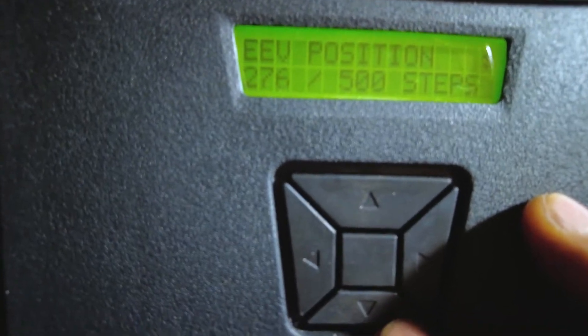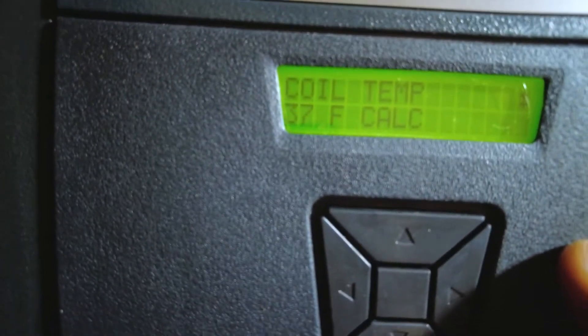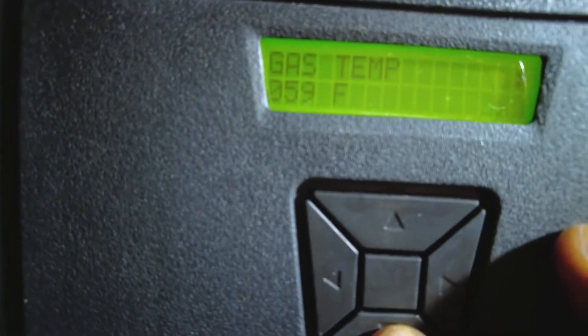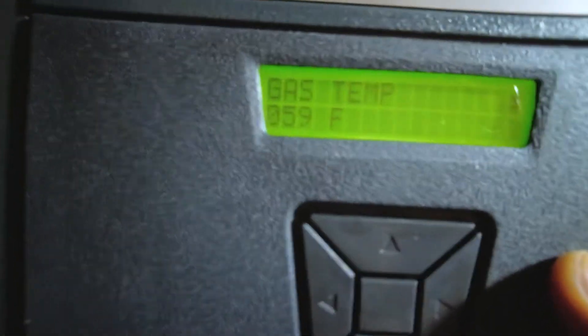It's about 50% open now, 276 steps. Coil temperature is 37 degrees right now. It's been running for about 5 minutes so far. Gas temperature is 59. So now you can see — before, that was reading like 126. That's pretty much it.